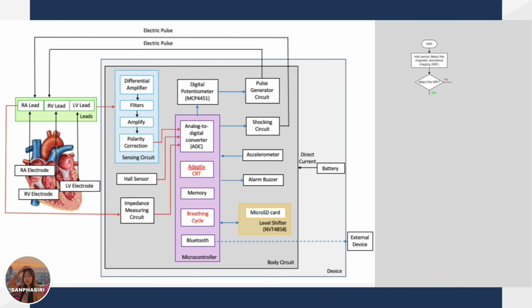When the magnetic field is detected, each mode is selected by the condition of the patient, whether pacemaker dependent or independent. The first mode is asynchronous pacing for pacemaker dependent patients, to pace at a specific rate and time.